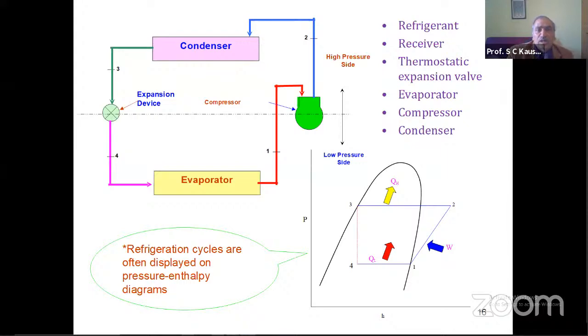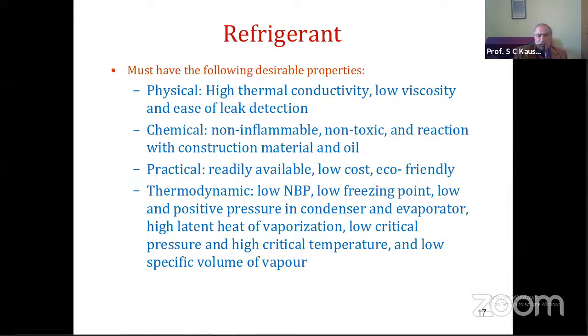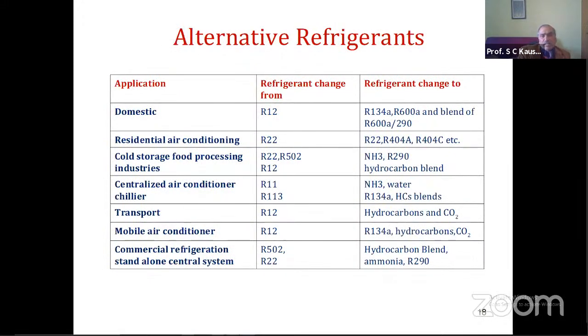So for the desirable refrigerants needed in these systems, there are certain physical, chemical, practical and thermodynamic requirements. Although we can meet these requirements, from the environmental point of view, as I mentioned, and from the energy requirement point of view, these refrigerants are not suitable. So we have to look for alternative refrigerants, and these are the alternative refrigerants which are recommended. But with the alternative refrigerants, the cooling capacity and the cooling COP achieved are not very high. So we have to go for multiple effect or multi-stage vapor compression systems as well.